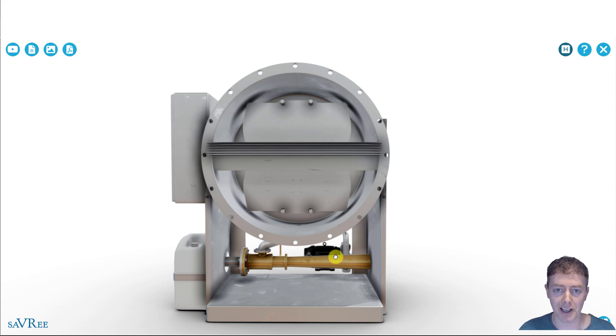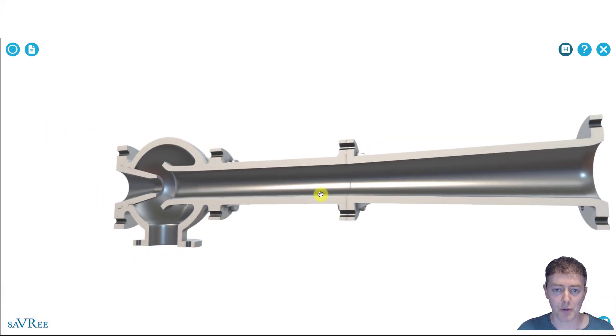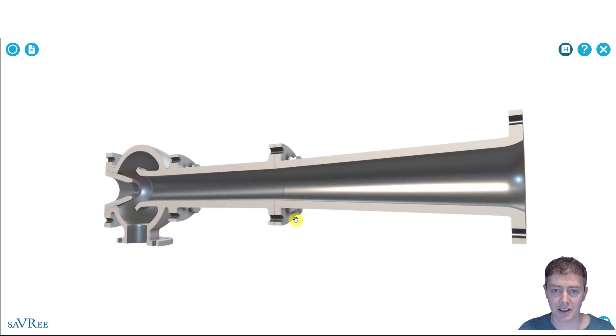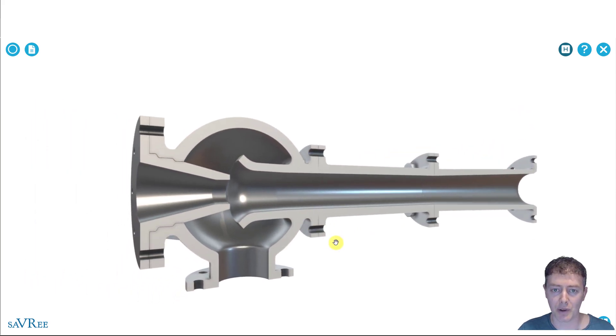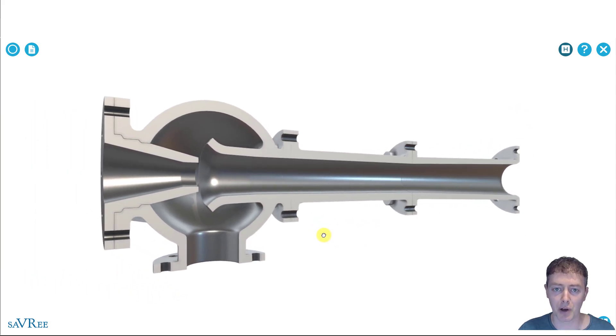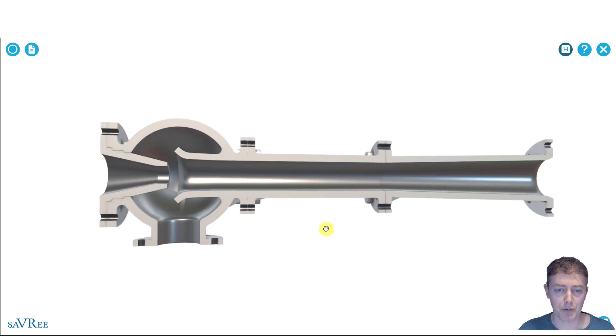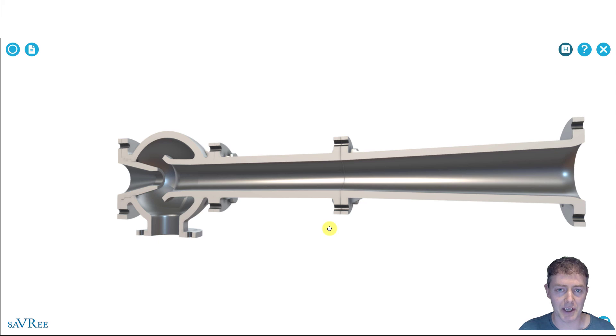Because there are no moving parts and no electrical connections, you can also use an eductor in hazardous environments. For example, if installing it within an explosive environment where it must be intrinsically safe, this eductor might be a very good alternative to using an electric pump. They can also be used for different fluids — including liquids, gases, slurries, and things like that — so they have a wide range of applications.